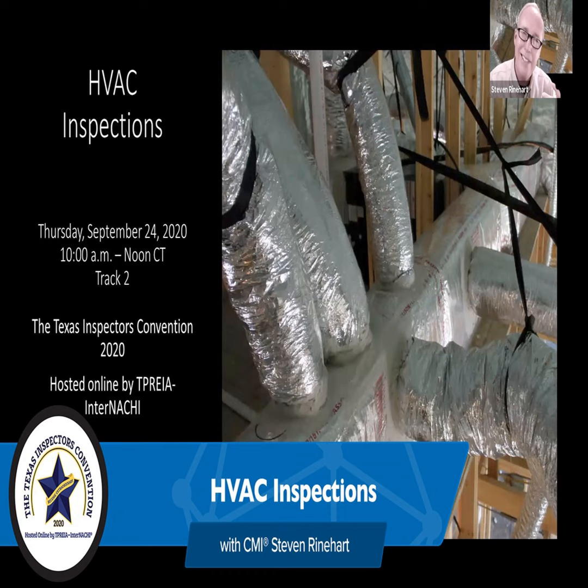The first thing I usually do is go make sure it has power. Does the air handler have power? Does the condenser? Has everything got electricity? So I look at that. So is it inoperative? Sometimes you turn it on, the air handler cranks up, the fan starts blowing, and you go, cool. Well, the second half of that is, on a split system, go outside and see if the condensing unit is running. I've had people pull the disconnect. I've had people steal the plug in the disconnect. Now I'm in trouble. I can't fix that because I don't carry spares with me.